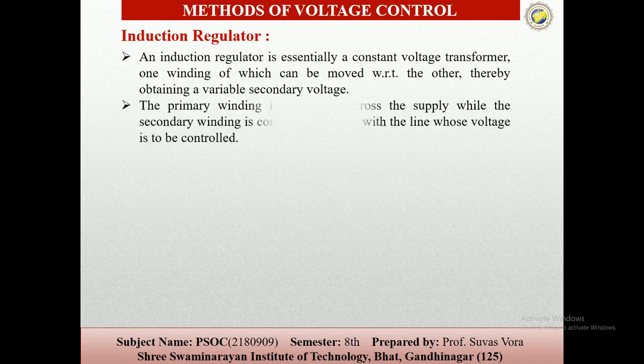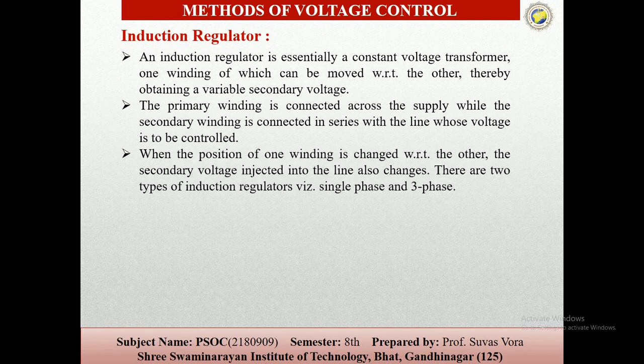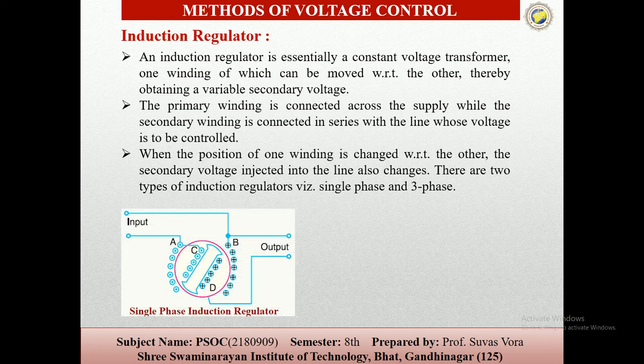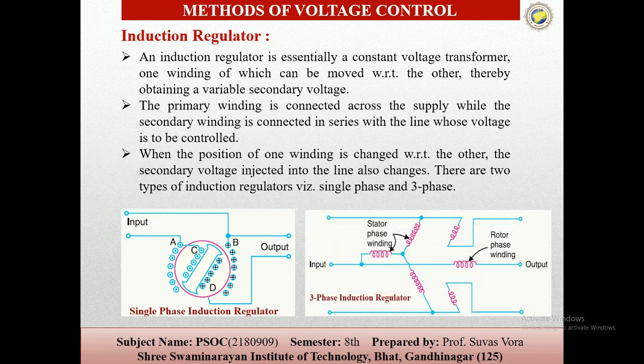There are two different types of induction regulators. When the primary winding position is changed relative to the other, the secondary voltage injected into the line also changes. The first one is the single phase induction regulator and the other one is the three phase induction regulator. You can see here the regulator in a single phase system, and here the rotor phase winding; this one is the stator winding.